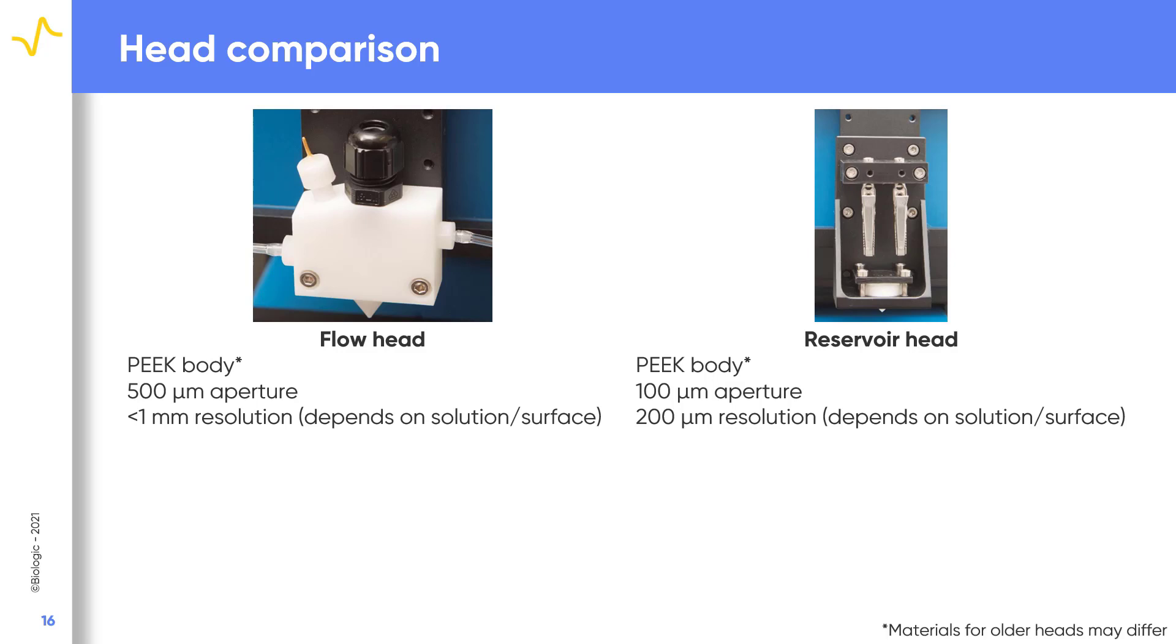On the other hand, the reservoir head has a smaller aperture of 100 microns, which improves the resolution to around 200 microns. Again, the final resolution of the technique, even with this head, is dependent on the solution and sample used.